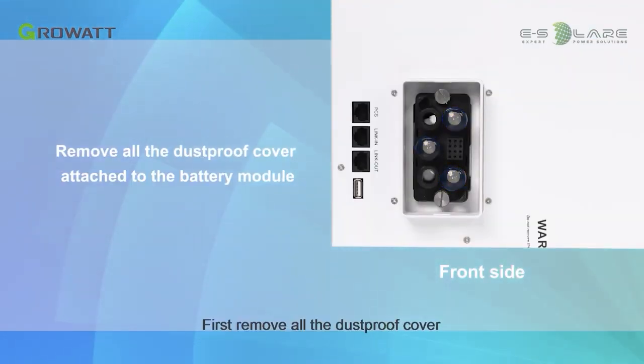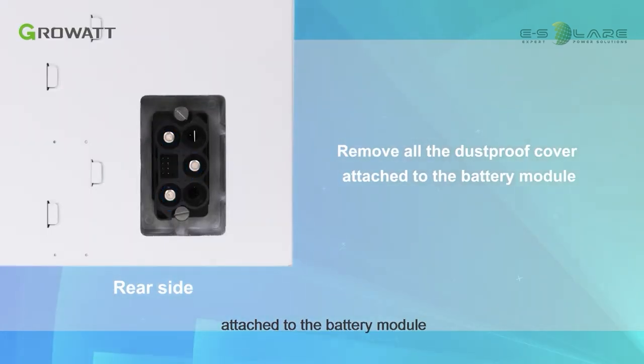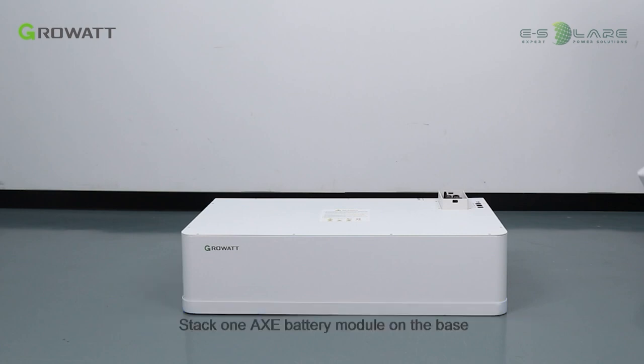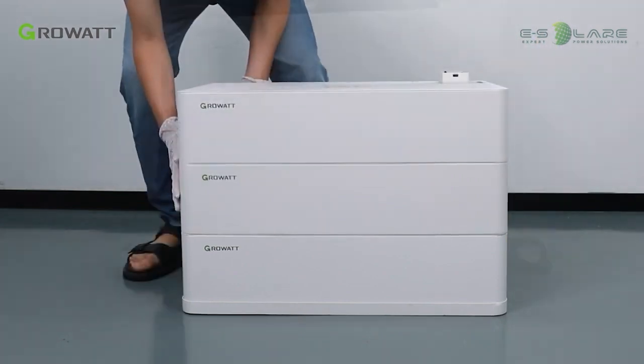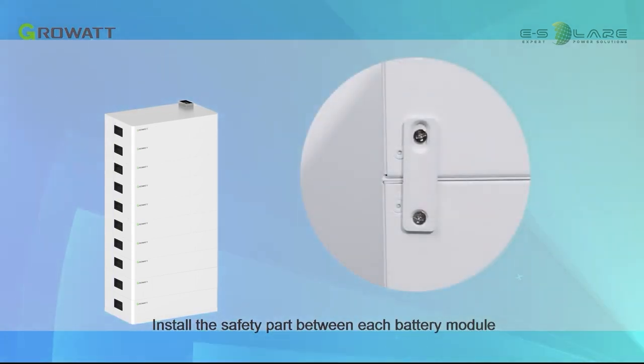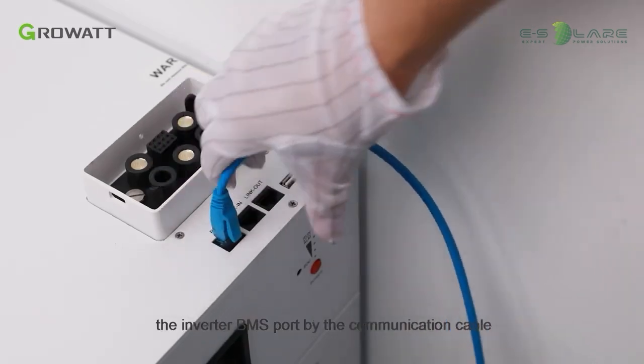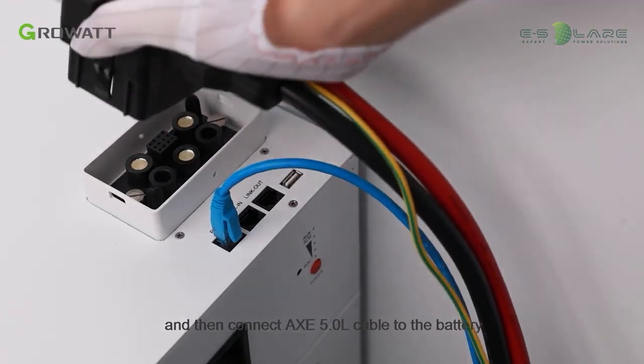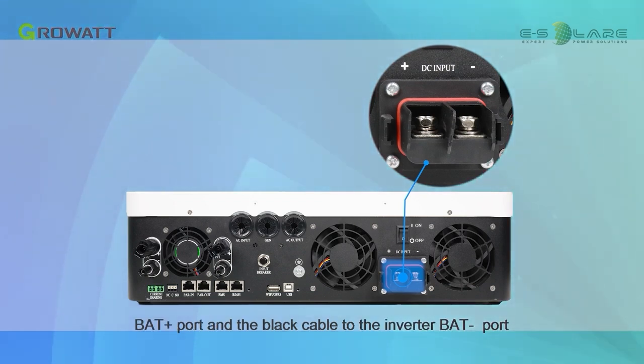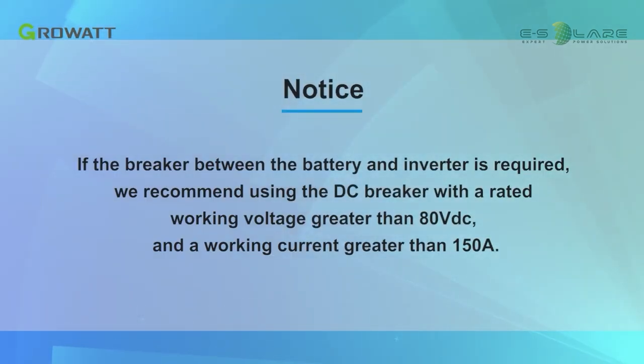For AXE battery installation, first remove all the dustproof covers attached to the battery modules. Adjust the AXE battery base to ensure it sits on the floor horizontally. Stack one AXE battery module on the base, then stack the second and additional modules. The maximum stack number of battery modules is 10. Install the safety part between each battery module. Connect the PCS port of the top battery module to the inverter BMS port using the communication cable, then connect the AXE 5.0L cable to the battery — the red cable to the inverter BAT positive port and the black cable to the inverter BAT negative port. Note: if a breaker between the battery and inverter is required, use a DC breaker with a rated working voltage greater than 80 VDC and working current greater than 150 amperes.